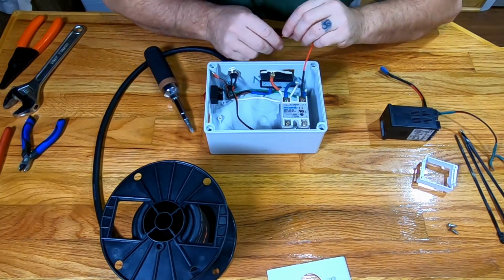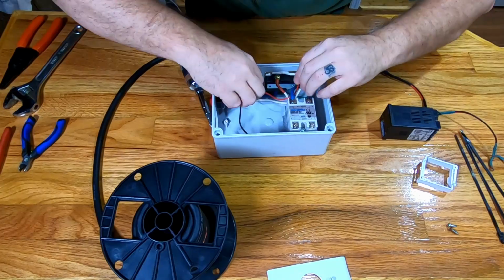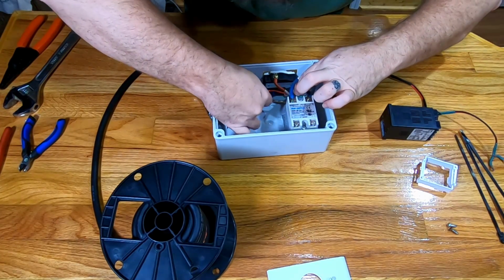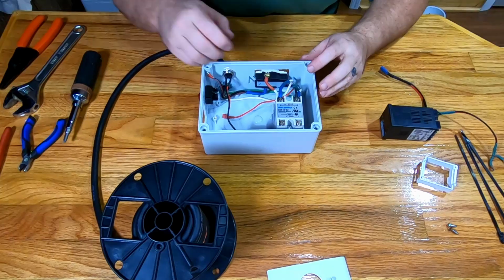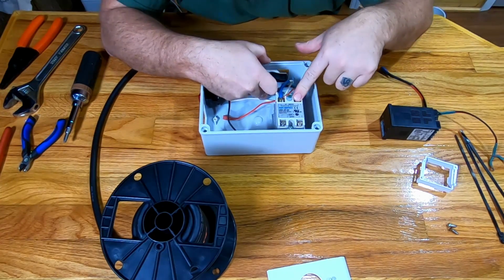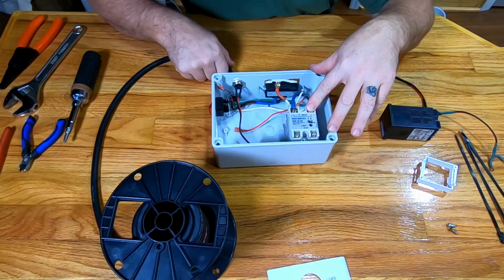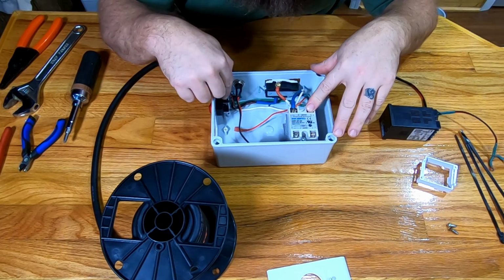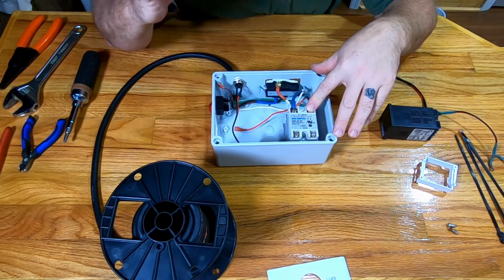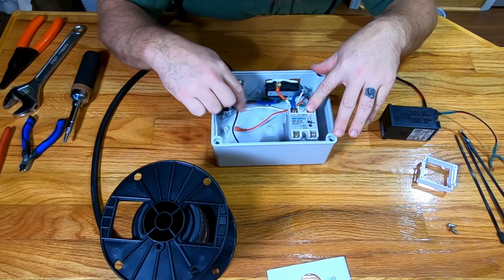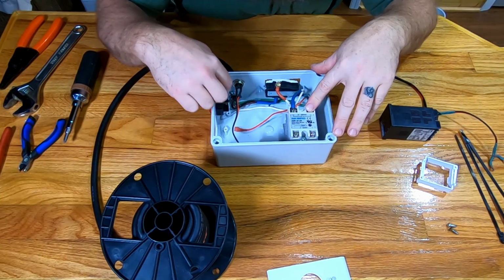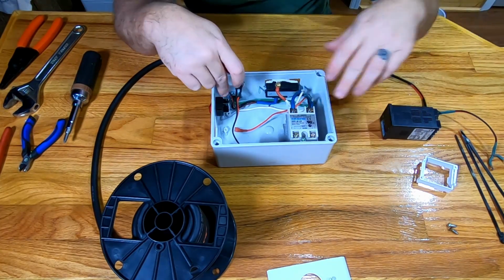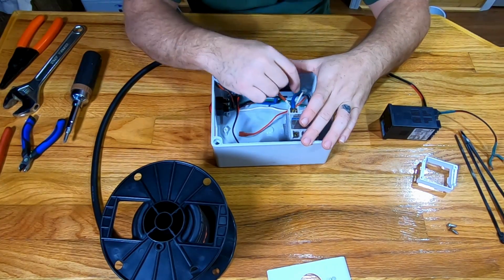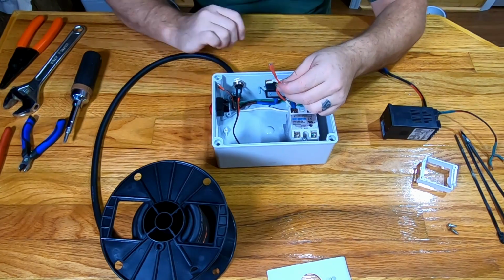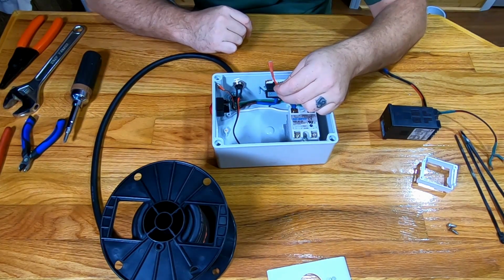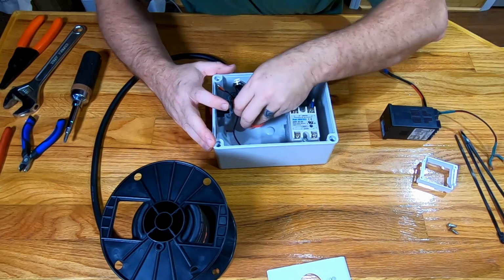That's going to send power from our 240 volt circuit, which is 120 on this side and 120 coming in from our outside main line. We send 120 to one side and 120 to the other side, giving us 240 total. But since we're only controlling the PID with this switch, we don't need 12 gauge wire. We're only drawing about half an amp, maybe 0.05 of an amp, so it's not very much power.